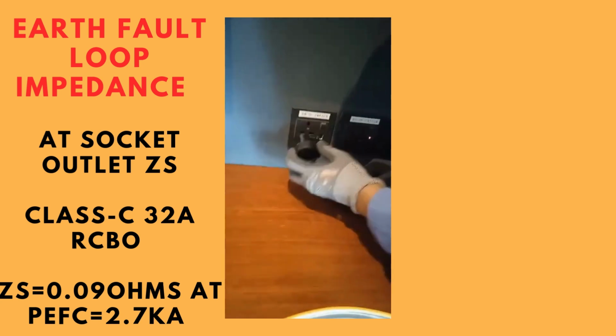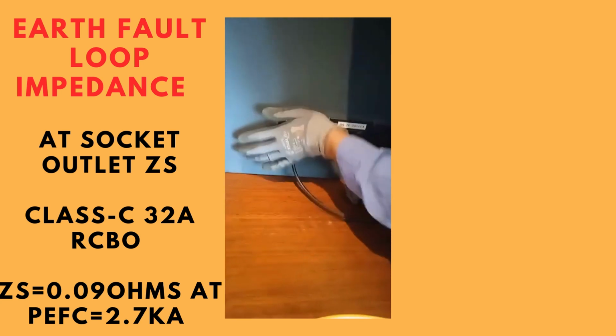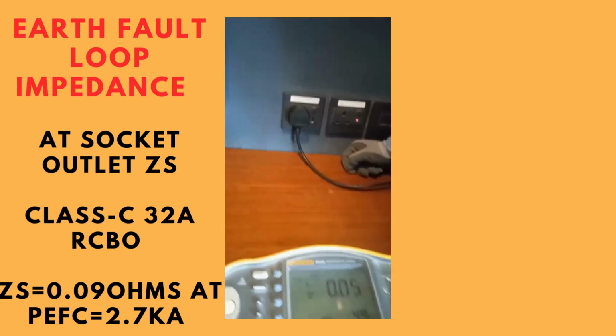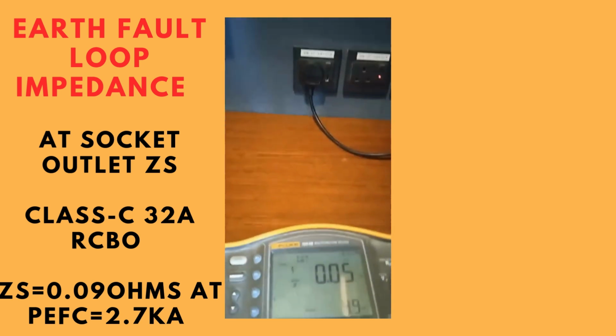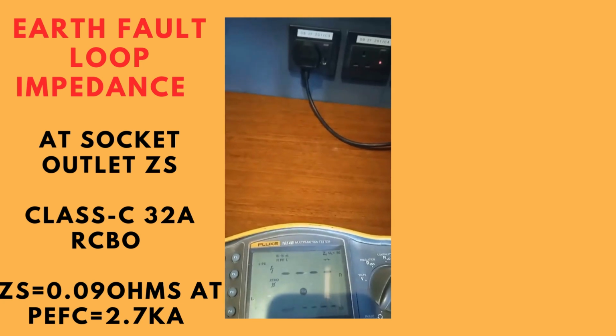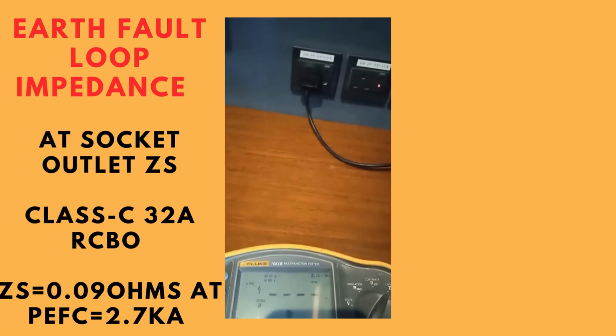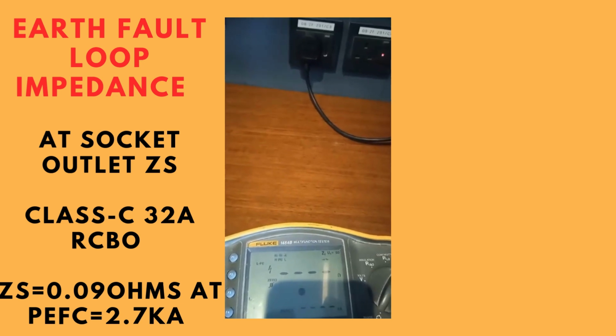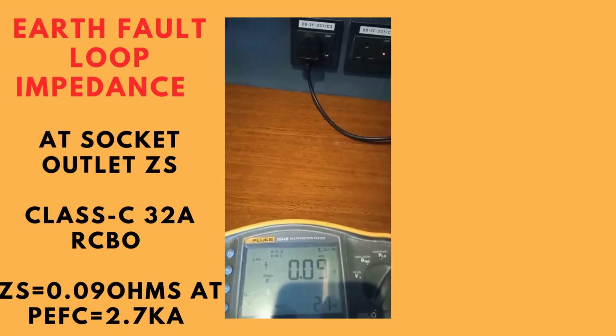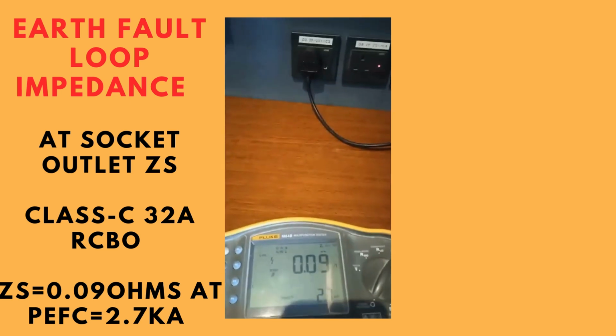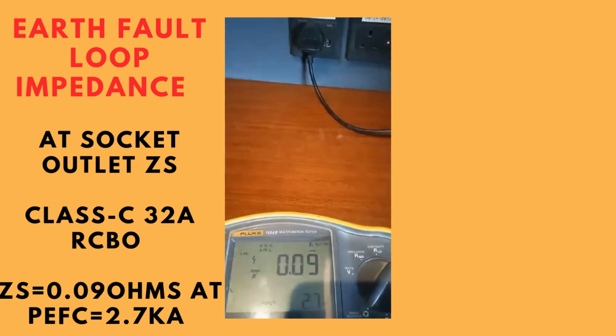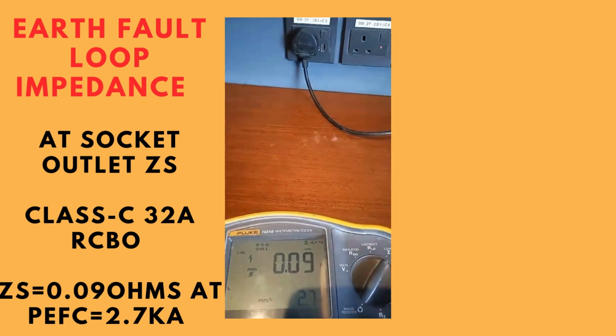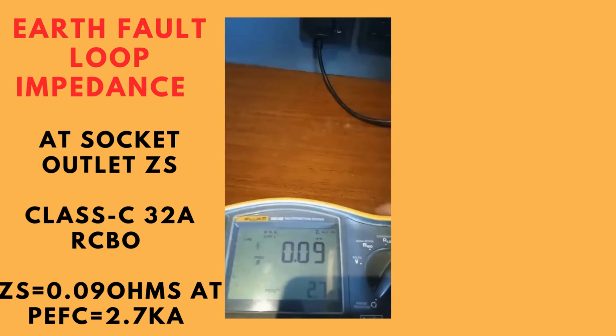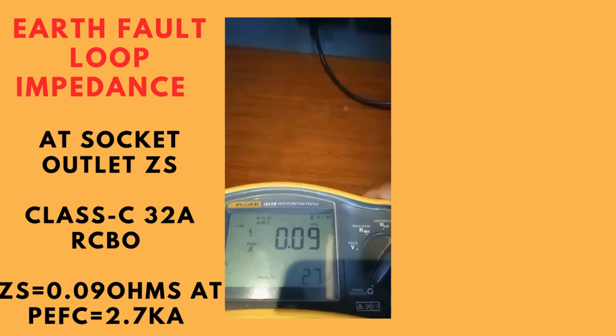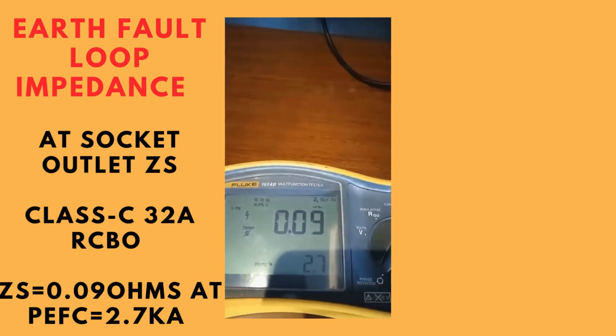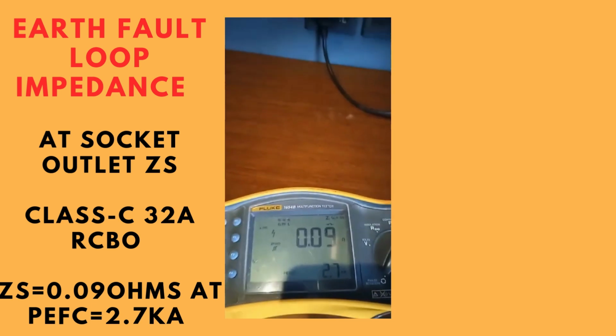So we are now carrying out the fault loop impedance test, which is the Zs. So we'll go to the furthest part of the circuit. I'd like you guys to comment down and give me the reason why we are testing at the furthest part of the circuit. So we are testing now. We have a fault loop impedance of 0.09 ohm, and we have a prospective fault current of 2.7 kiloamps. So we move.